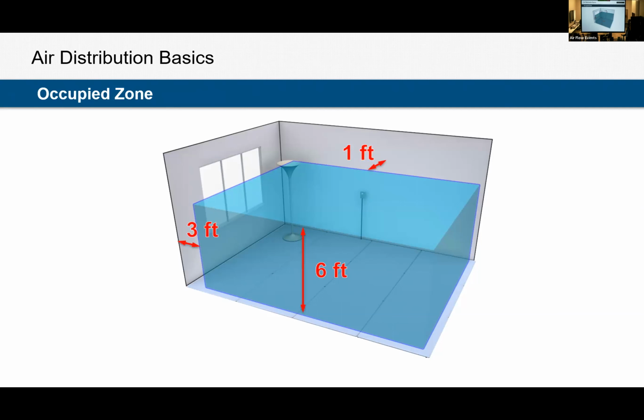In a mixed system, or just in any space in general, when we're designing, we are designing only for the occupied zone. The occupied zone is 6 feet off the floor, 3 feet from an exterior wall, or 1 foot from an interior wall. Anybody who's over 6 feet tall, we're not conditioning their head. We're only concerned with 6 feet off the ground.